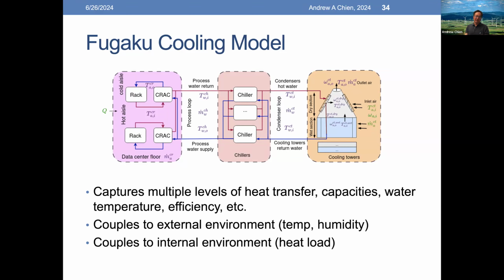So this couples to the external environment. We can set the external temperature and the external humidity, which affects, as shown here, the efficiency of the cooling towers. And it couples to the internal environment in that based on what the requested heat load is, then we generate an optimum configuration, because now you're choosing temperatures and flow rates across all of these different parts of the cooling infrastructure to determine how to best realize the heat transfer that you need to achieve, and therefore the PUE that you're actually achieving when you're running at that particular capacity for that particular external environment.